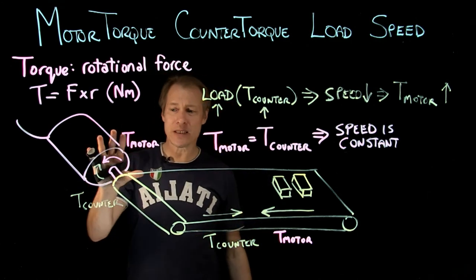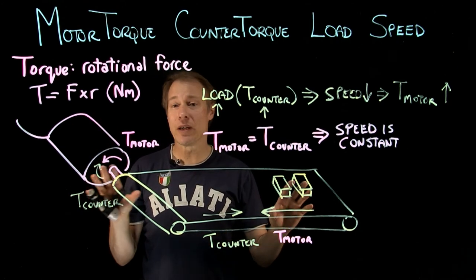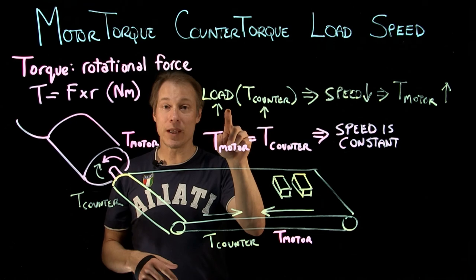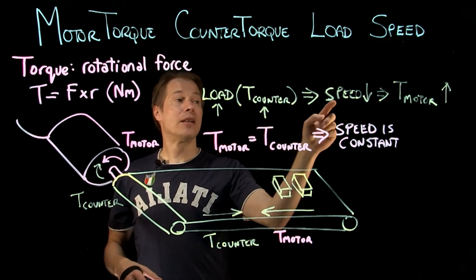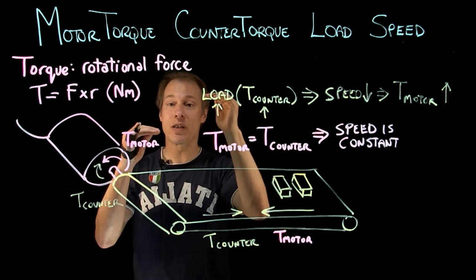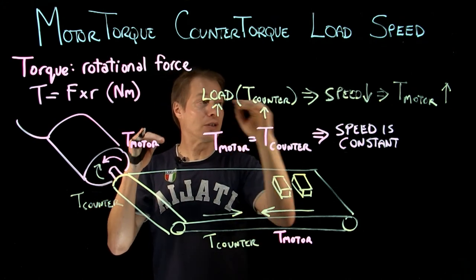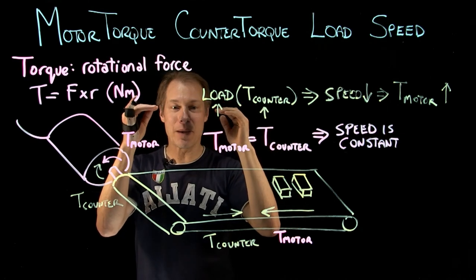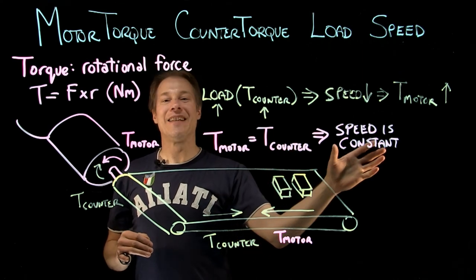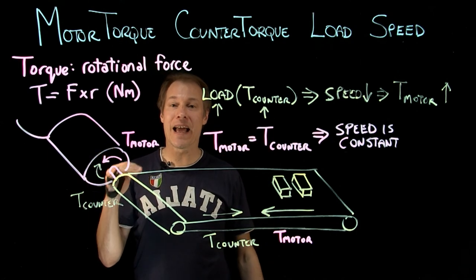Let's try that one more time with a concrete example. We have this motor running at a constant speed. I put more load on it — in this case, bricks. The load goes up, which means the counter torque goes up, and since the counter torque is now higher than the motor torque, the motor slows down. When the motor slows down, the motor torque goes up. When the motor torque reaches the counter torque, the speed becomes constant again — slower than before, but constant.